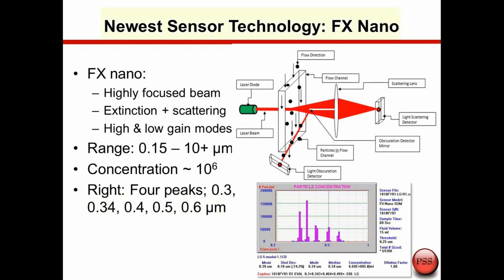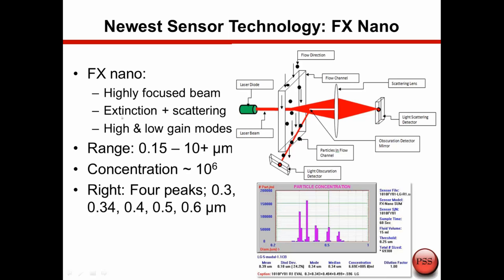The next development was the FX nanosensor, which again uses a focused laser beam for higher intensity. In this case we have both an extinction and a scattering detector. With the higher intensity laser beam and the scattering detector, we can now measure down to smaller particle sizes — down to 0.15 microns or 150 nanometers. The FX nanosensor has a dynamic range of 0.15 to about 10 microns and can also measure at very high concentrations up to 1 million particles per ml. The graph on the lower right shows that even with the deconvolution program we can still resolve multiple peaks — 0.3, 0.34, 0.4, 0.5, and 0.6 microns resolved to baseline — making it a very high resolution technique.